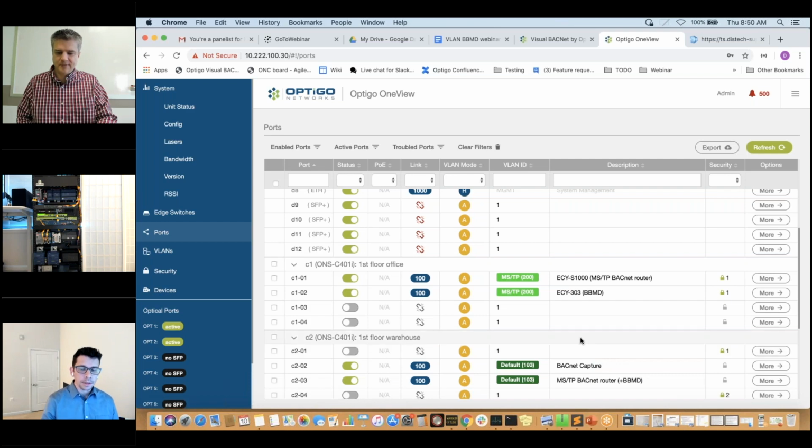Most modern controllers, if they see the network go down, when it comes back up, they'll ask for the address again. But just keep in mind, there's always potential. If you change these, you may have to power cycle a device or wait for the DHCP lease to expire. And so this is one reason not to have excessively long DHCP leases on a network.